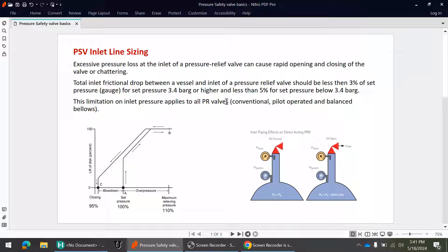First of all, what happens when there is a pressure drop in the PSV inlet line? Due to excess pressure loss in the PSV inlet pipeline, there is chattering — rapid opening and closing of the PSV. Due to this rapid opening and closing, the PSV seat will be damaged and we have to replace it, so maintenance cost will increase. To avoid this chattering issue, we should size the PSV inlet line so that the inlet line loss does not exceed the limit.